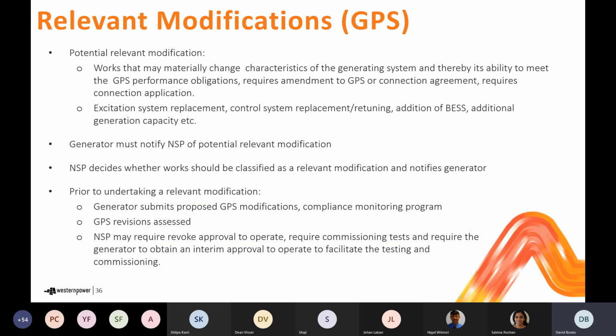Depending on the significance of the change, the network service provider may choose to revoke your approval to operate and require instead that sufficient commissioning tests are undertaken to demonstrate that the generator, with the relevant modification in place, is able to meet the required performance standards. Often, to facilitate those tests, will require the process of granting an interim approval to operate. Once the tests are successfully undertaken, that rolls over into a reinstatement of the approval to operate. Those approval to operate mechanisms are a new process that's been introduced through revisions to Chapter 4, to be consistent with an equivalent framework introduced through the revisions to the WEM rules.